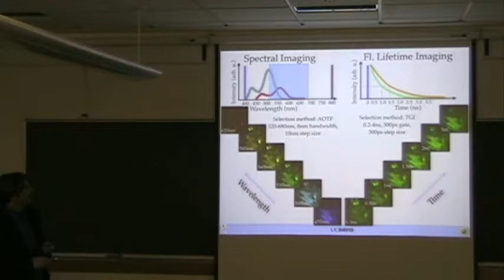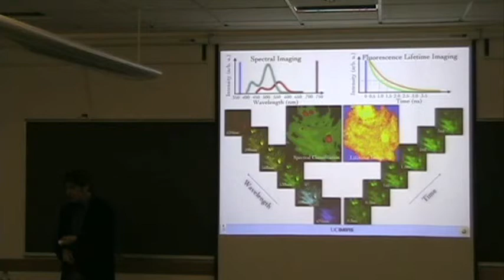The spectral range, 520 through 620 to 680, and other technical details are here. But important is that you can then do classification, you can do spectral reconstruction, and you can put together an image that contains spectral information on each pixel. So on each of these pixels, you can tell not only the morphology of the object, but also the spectrum of that object. You can do spectral classification by selecting one specific spectrum and then doing linear discriminant analysis on that spectrum to see what other spectra look the same, and then you create a whole spectral map. The same you do with fluorescence lifetime imaging. So this is just to show that this was possible.